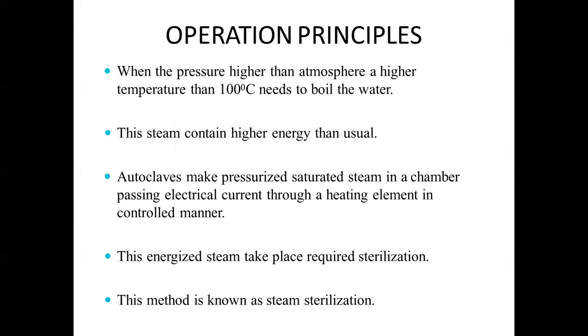to boil the water. So this steam contains higher energy than usual. तो यहाँ पर क्या करेंगे, autoclave makes pressurized saturated steam in a chamber passing electrical current through a heating element in controlled manner. This energized steam takes place required sterilization. So this method is known as steam sterilization.